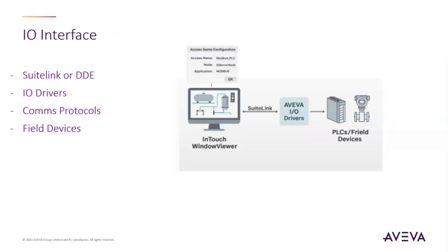So that's the first part, the WindowViewer communicating with the drivers through the SuiteLink protocol. But then this driver itself should connect to the PLC and speak the language of the PLC. So the driver acts as a protocol translator - it maps the logical requests received through SuiteLink into the appropriate dedicated protocol used by these field devices.